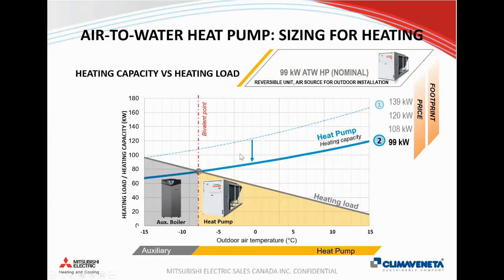And this is one of the reasons why it's called an applied product. It's not just a magic box that you can put on the roof of your building and supply heat at all times. You really need to understand how the building is going to perform and behave and select the heat pump so that you have the best combination of things. And again, remind yourself of what the objective is here. If you're trying to do net zero carbon designs, then this is the approach that we're going to have to take. So we have more details coming up as well. So again, bivalence point, that's one of the keywords. Bivalence point just means you're changing over to an auxiliary heat source at a certain temperature.